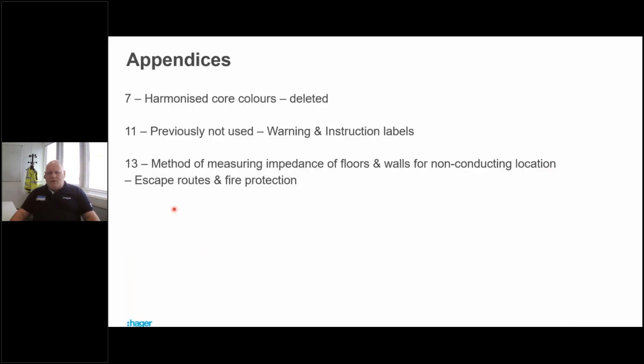Appendix number 13. It's given us a method of measuring impedance of floors and walls for non-conducting locations. And it mentions escape routes and fire protection. But that also could include hospital operating theatres. It could incorporate electronic labs where we want a non-conducting covering on the floor and walls. Okay, so that gives us the method for measuring this in these areas. So it's always worth a read in these areas.